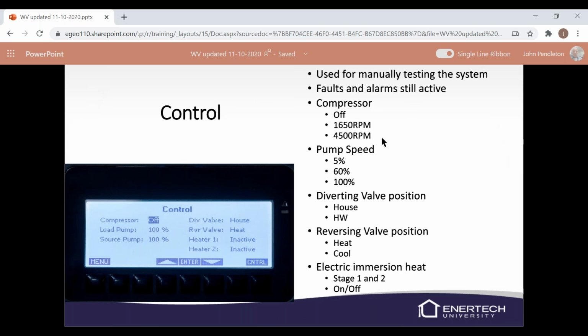Control menu, again, you can go in here, you can turn the compressor off, you can set it at a certain RPM. If you're having problems with the unit, it's probably best to go in there and set it at a fixed speed so that it's not bouncing around trying to adjust. So this control will be to manually test the system. You can put your pumps in 5, 60, or 100%. You can switch your diverting valve, reversing valve, and your electric immersion heaters. So here you can go to the control menu and test out the system.